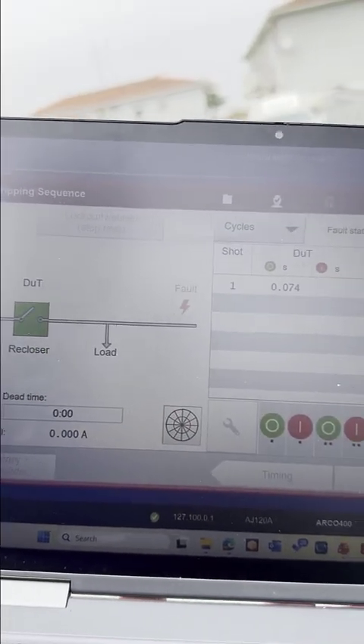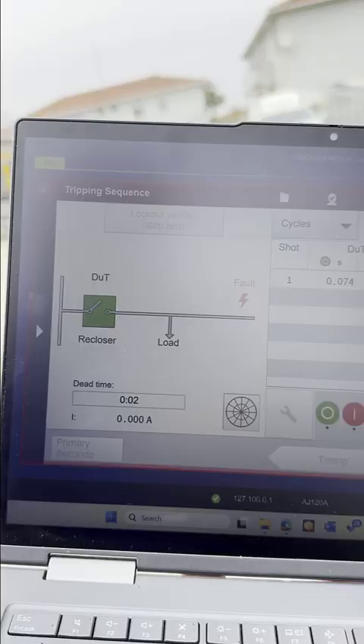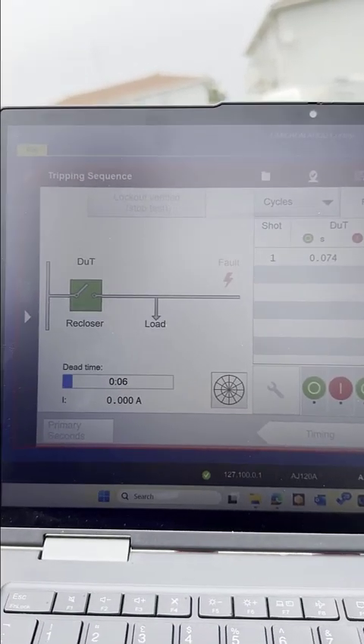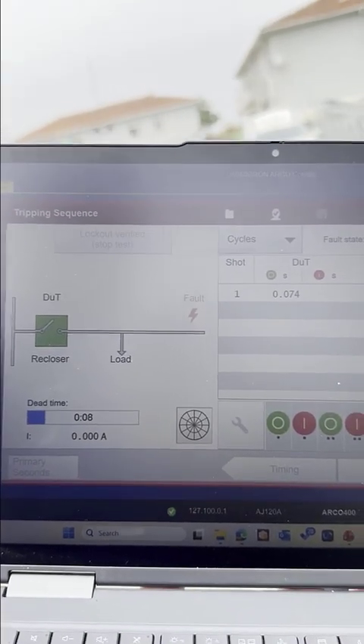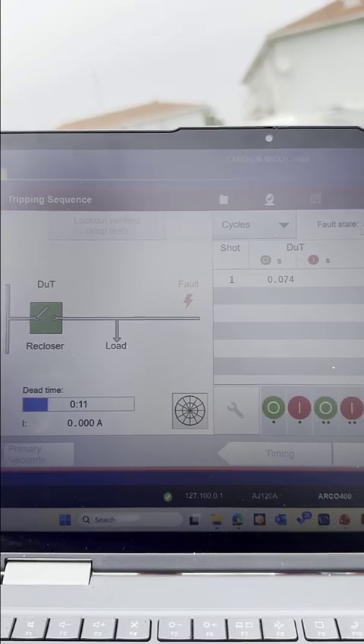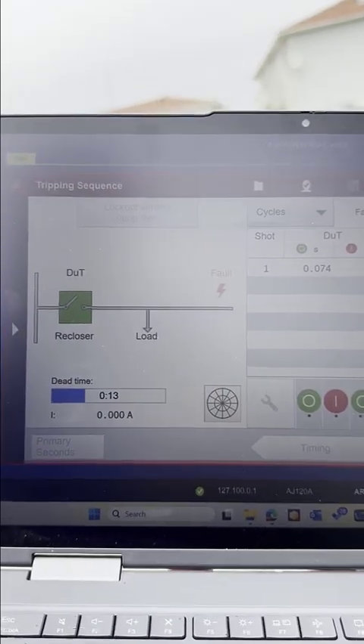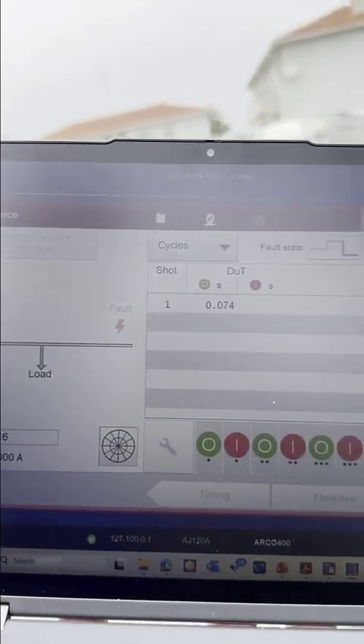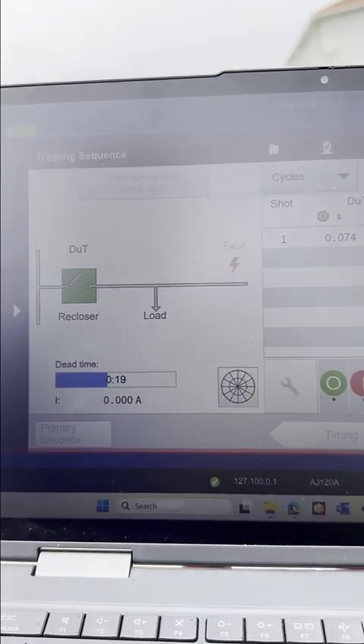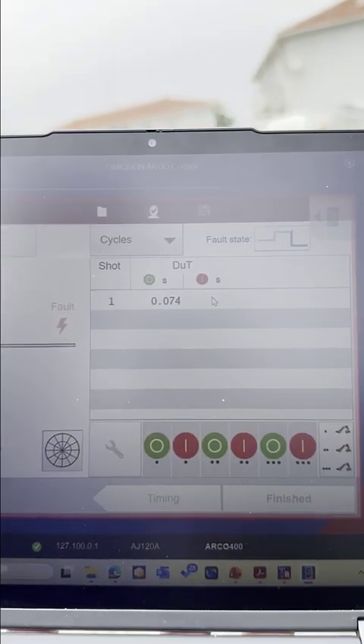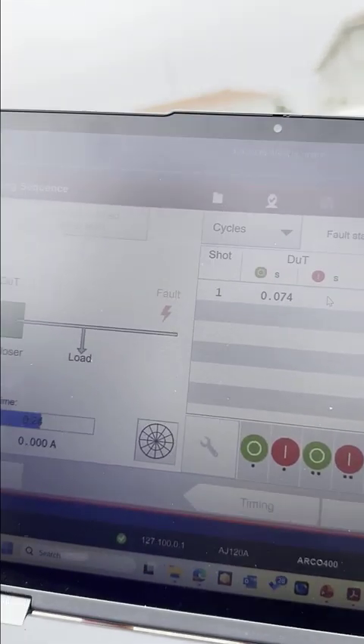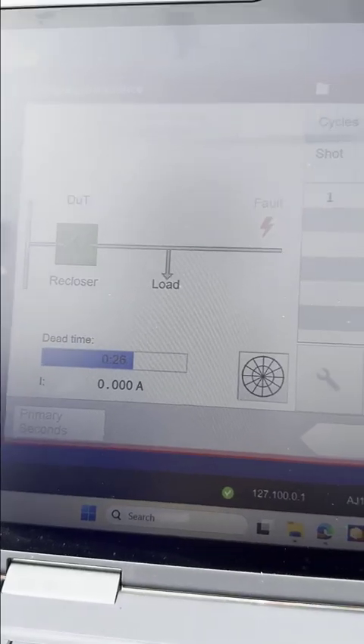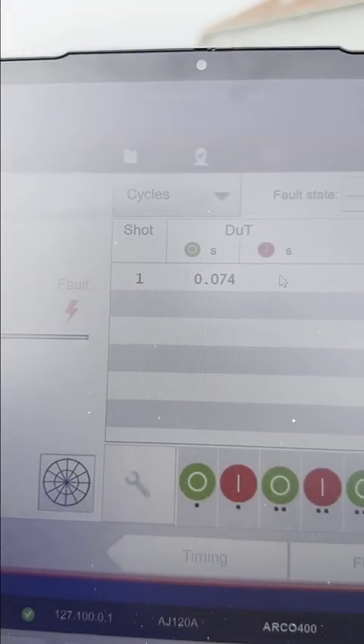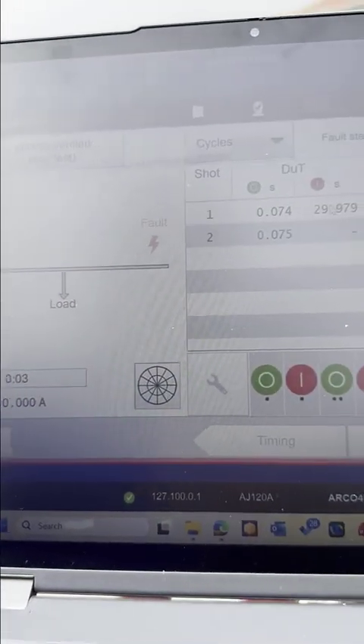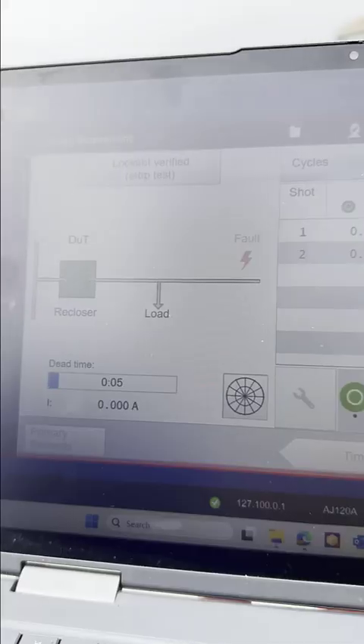Now the first trip happened after 74 milliseconds by the earth fault protection. Now it will count up to 30 seconds for the first shot of the reclosing. We will measure it here as you can see from this screen. Okay, so it's 27, 28, 29, now 30. So now it's closed. You can see now the second trip happened, at 75 milliseconds.